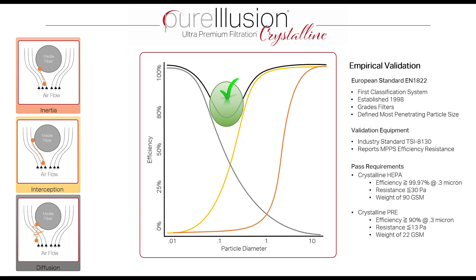EN 1822 is the first classification system developed in 1998 for HEPA filters. It grades HEPA filters — so on the side of a HEPA filter, you might see H12 or H13. The larger the number, the greater the efficiency of capture at 0.3 microns, the most penetrating particle size.